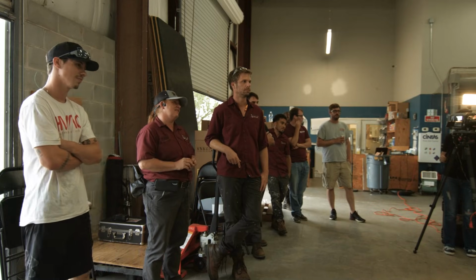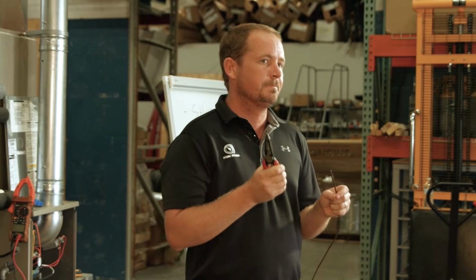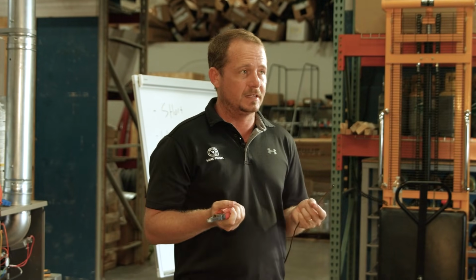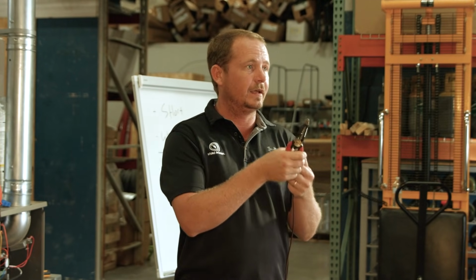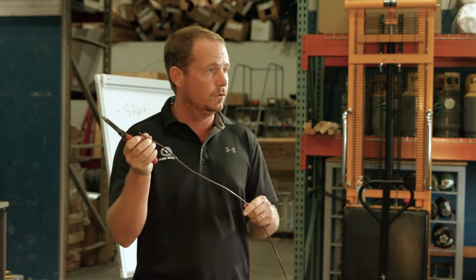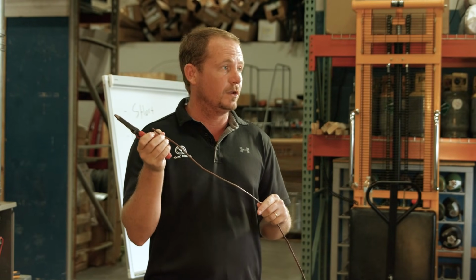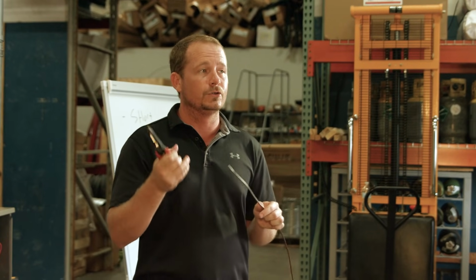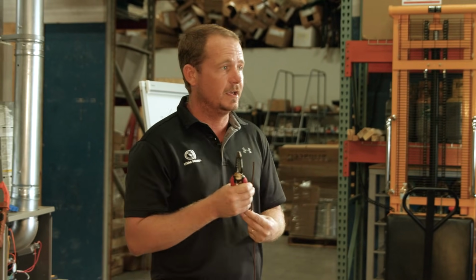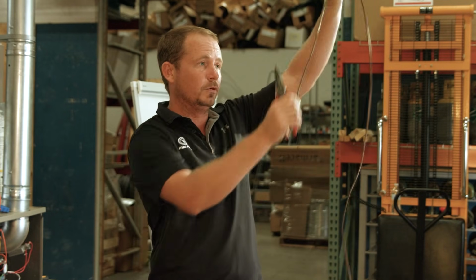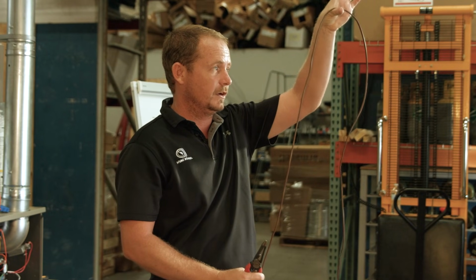The most common causes of problems, especially in newer installations, are what we just talked about: ringing it, nicking it, pulling it through, and nicking or scraping it as it goes through the equipment. In residential new construction, especially with metal studs, a common cause is pulling the conductor through a metal stud and chafing it.